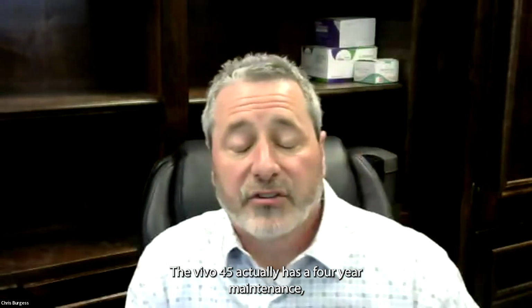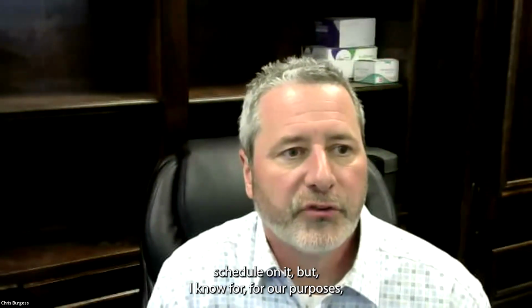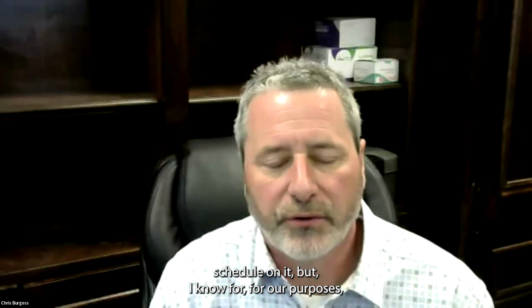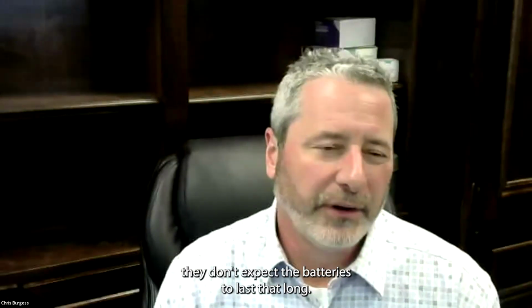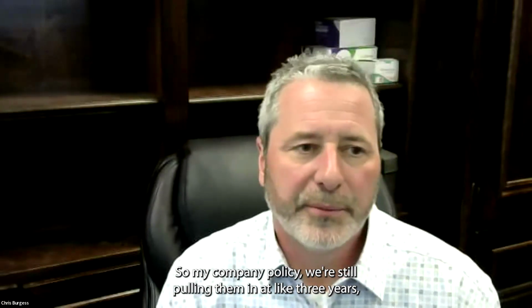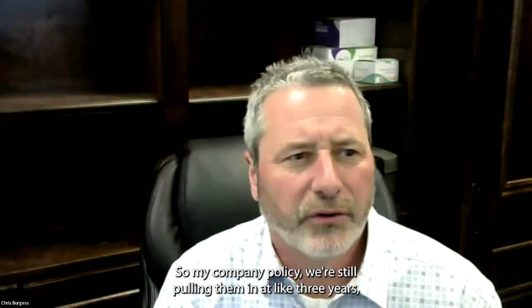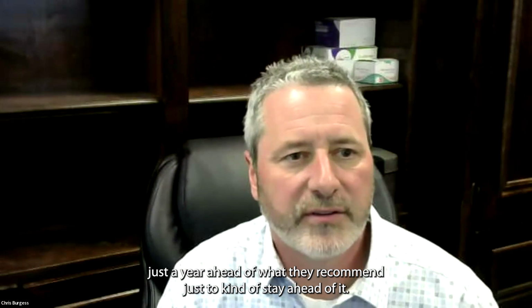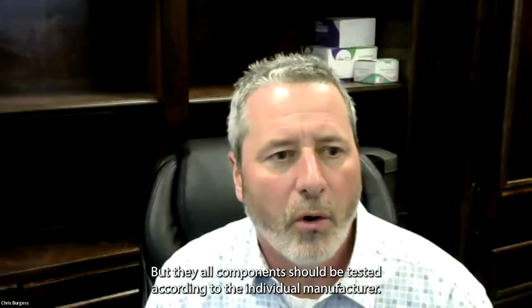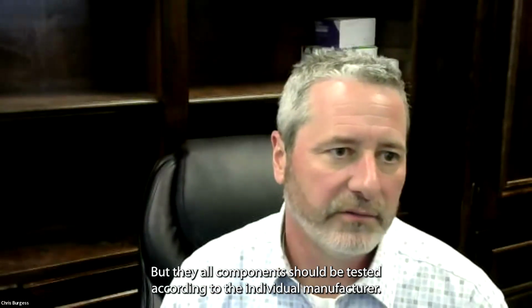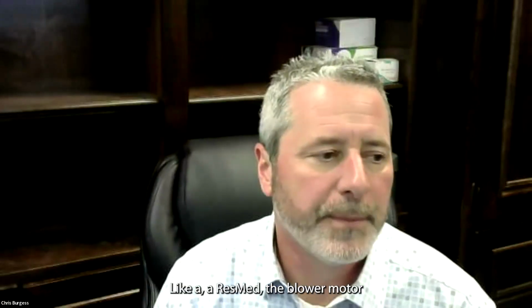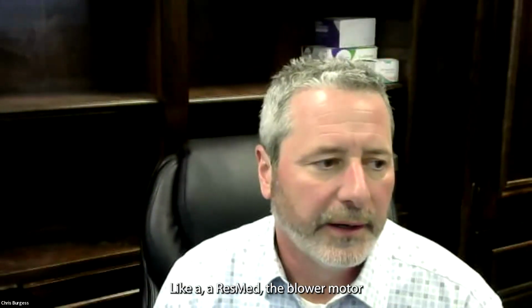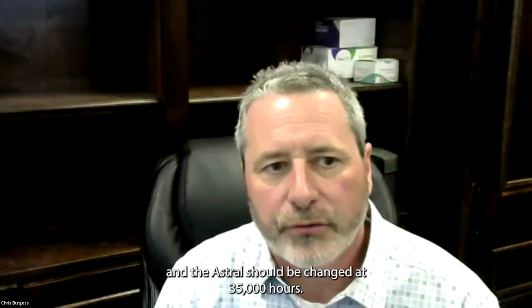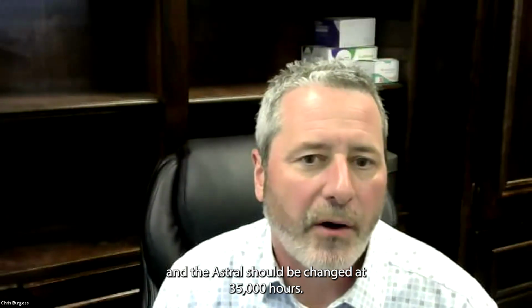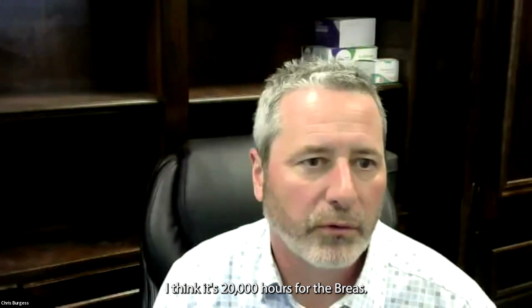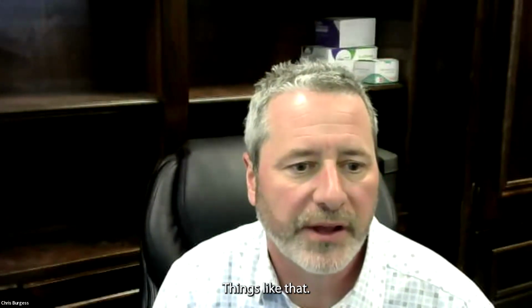The Vivo 45 actually has a 4-year maintenance schedule on it, but I know for our purposes, they don't expect the batteries to last that long. So my company policy, we're still pulling them in at like 3 years, just a year ahead of what they recommend, just to kind of stay ahead of it. But all components should be tested according to the individual manufacturer. Like a ResMed, the blower motor in the Astral should be changed at 35,000 hours. I think it's 20,000 hours for the Breas, things like that.